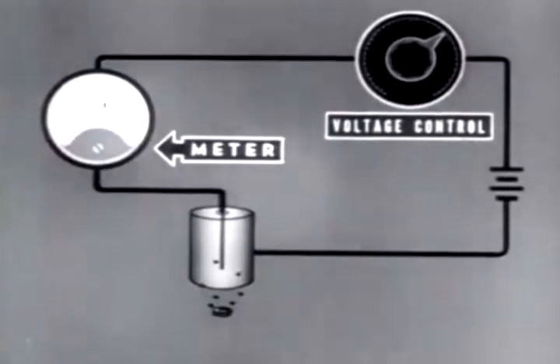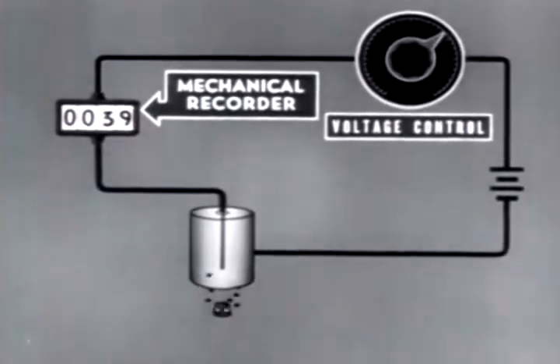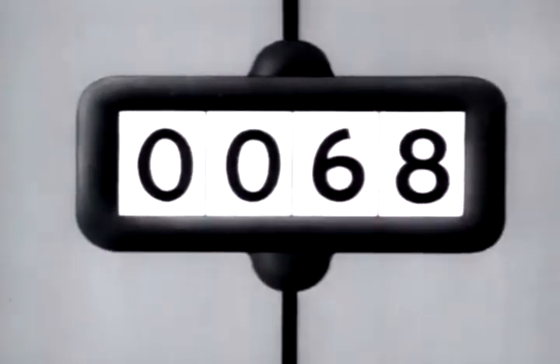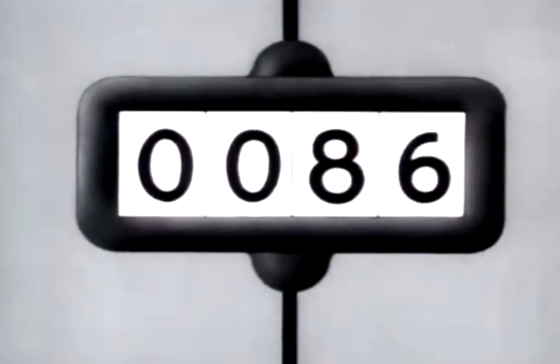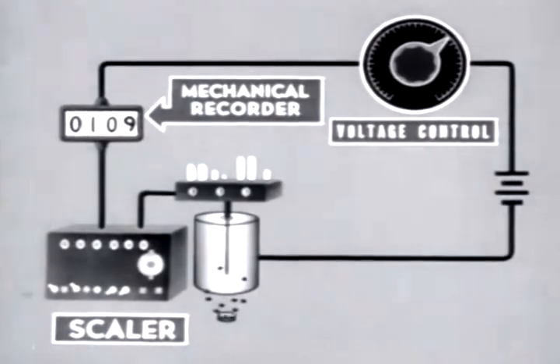In a Geiger tube, the occurrence of ionizing events can be seen by the pulsation of the meter. A mechanical recorder, actuated by the current pulses, is used to record the number of events; however, it requires larger pulses than are generated in the tube, so a pulse amplifier must be used. Another characteristic of the recorder is its inability to register more than a few counts per second. In order to provide for counting samples of high activity, a scaler is introduced into the circuit — an electronic device which passes on to the mechanical counter only one pulse for a certain number of pulses received from the tube. The proportion registered to those received is called the scaling factor.